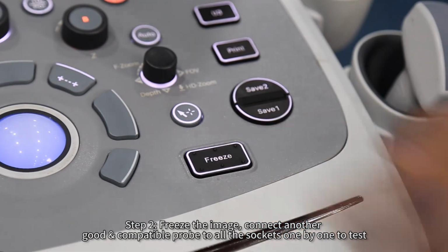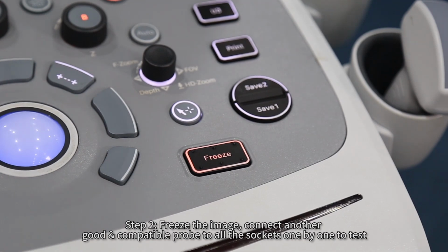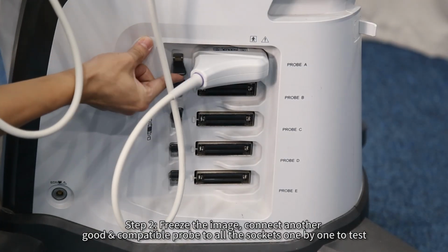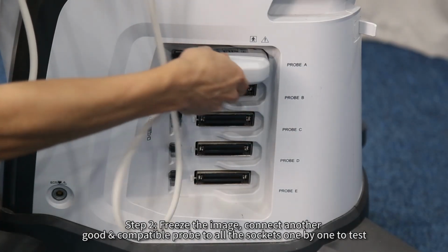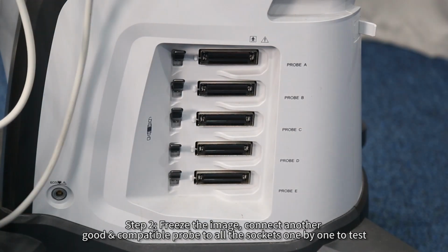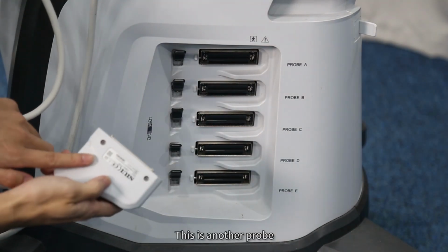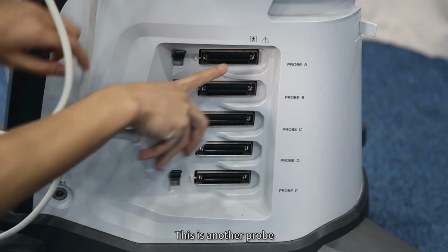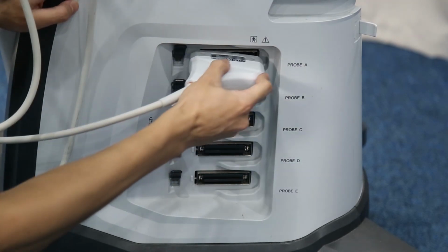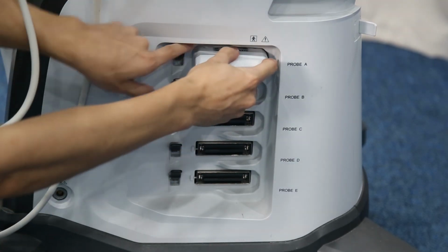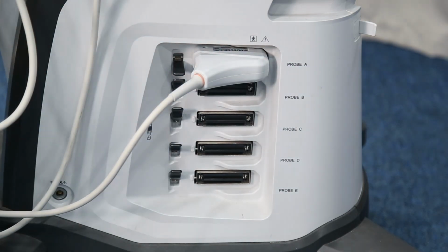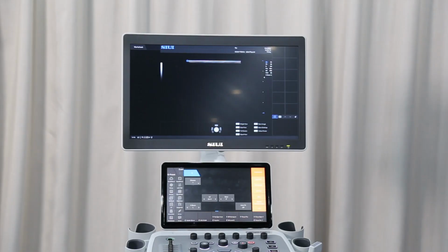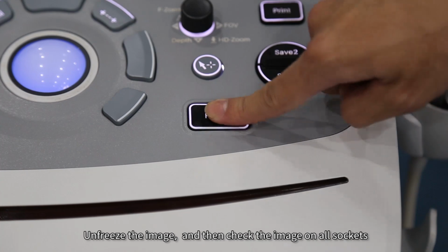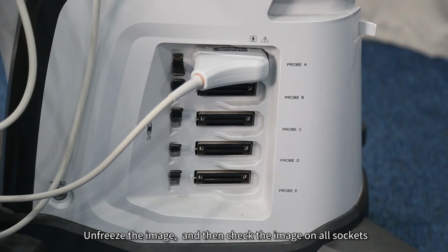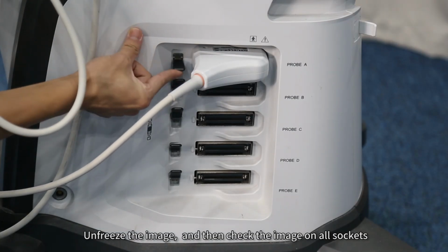Step 2. Freeze the image. Connect another good and compatible probe to all the sockets one by one to test. This is another probe. Unfreeze the image, and then check the image on all sockets.